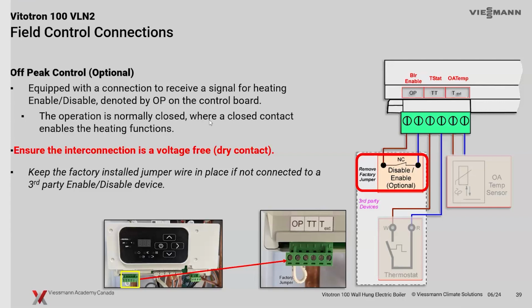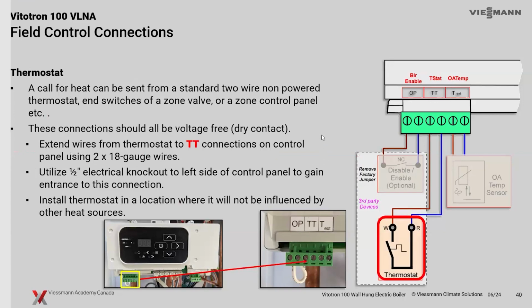So even if your thermostat closes and you've got a call for heat here, if that contact is open, it will disable the boiler. It will give you an indication on the boiler that it's not firing as a result of that. There's some diagnostics in here, but just so you know, it's available. Very simple contact for you to use should that be desirable. Of course, your TT contact here is a dry contact, potential free. We don't want any voltage on these contacts. The OP terminal here should be dry as well.